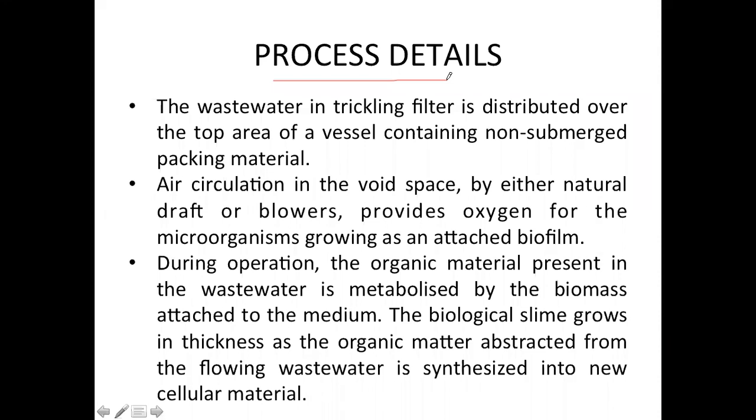One thing is also very important as with the activated sludge process. Here we will also use a secondary sedimentation tank with the trickling filter. So this is the main process involved here. The wastewater is distributed over the top area of a vessel containing non-submerged packing material.